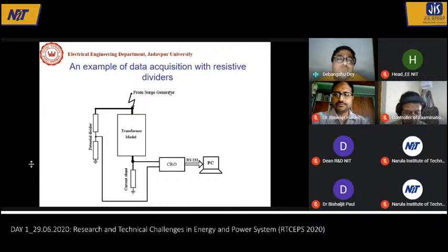Simply put, we have to apply some impulse voltage across the transformer winding, check what is the response current, and from that current understand whether there exists a flaw or problem in that particular transformer winding or not.